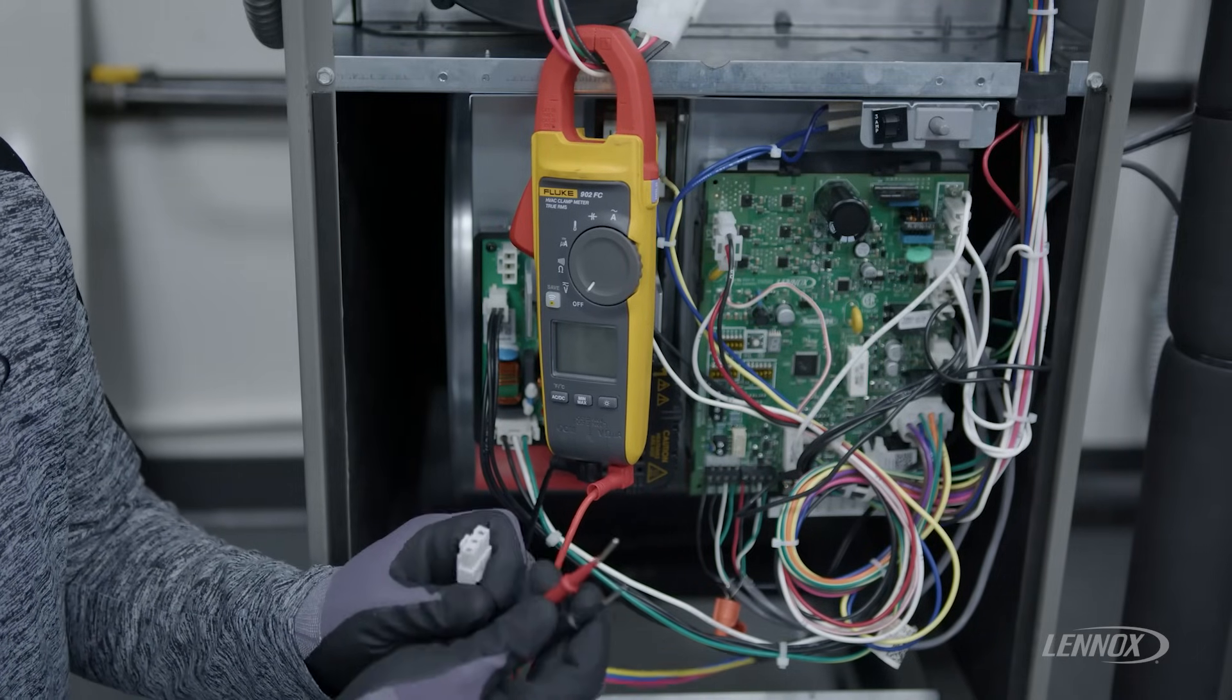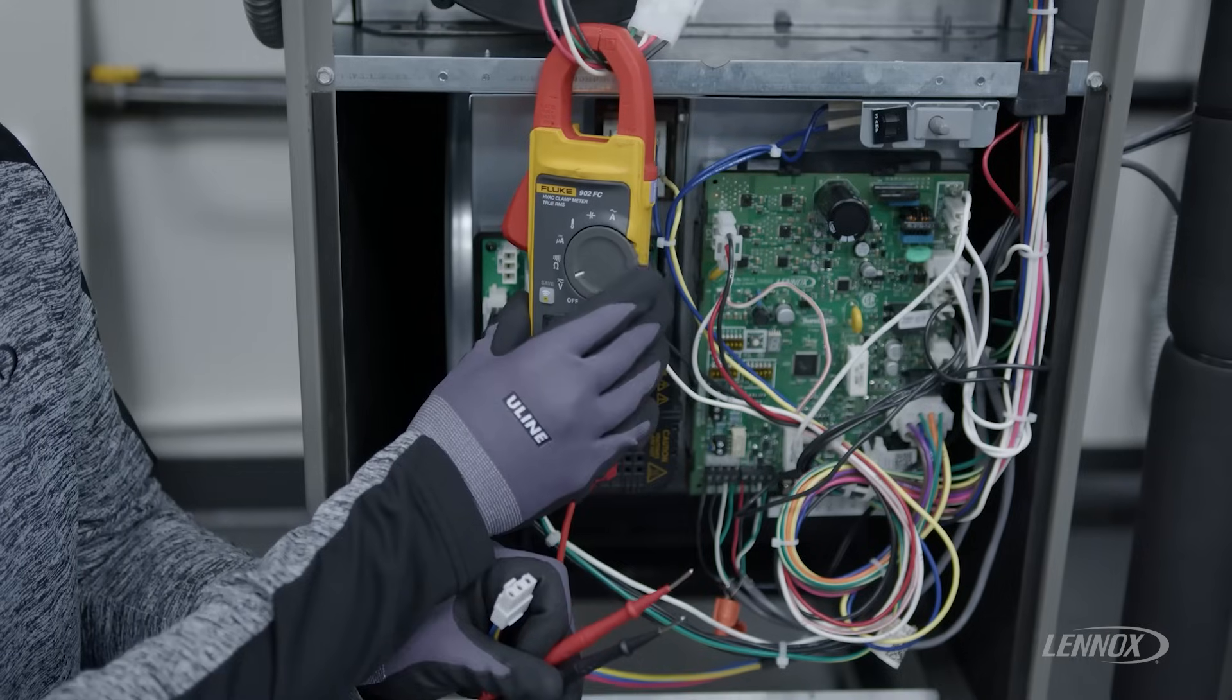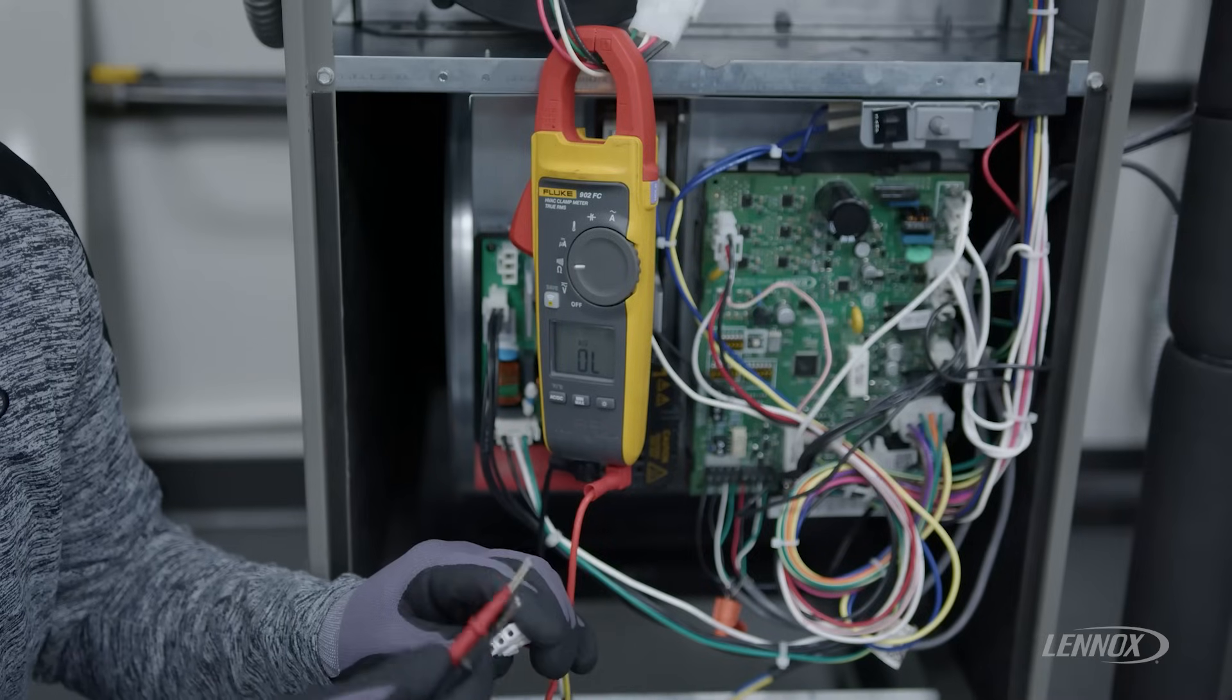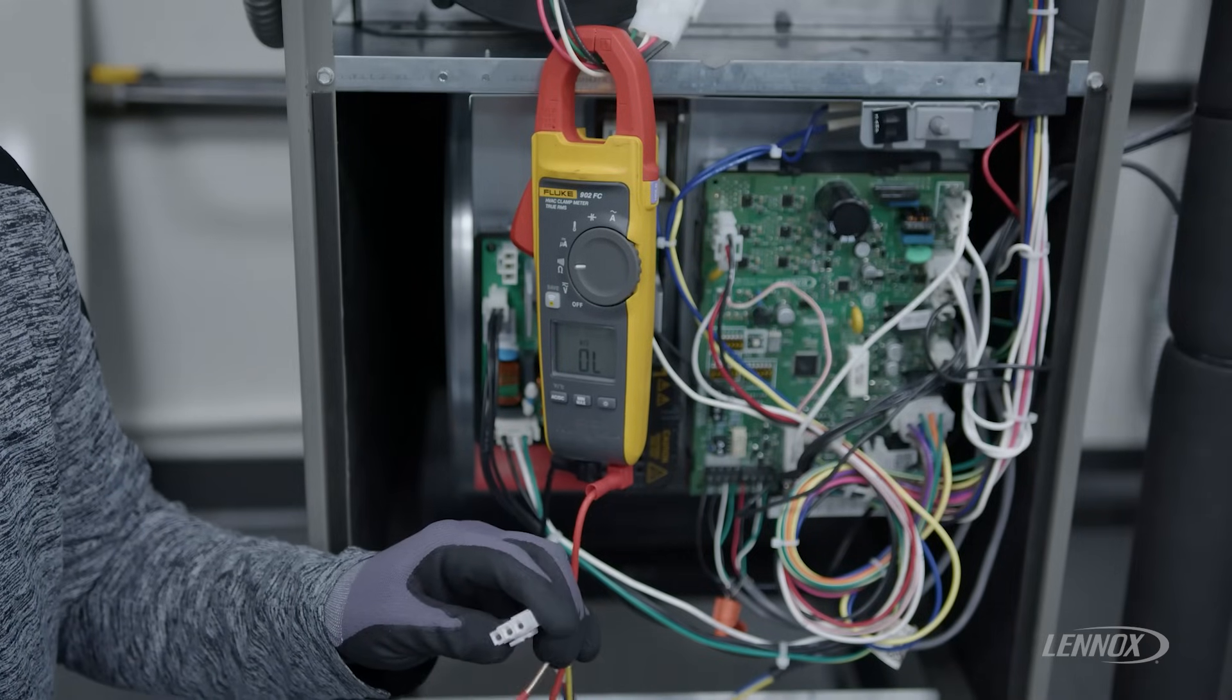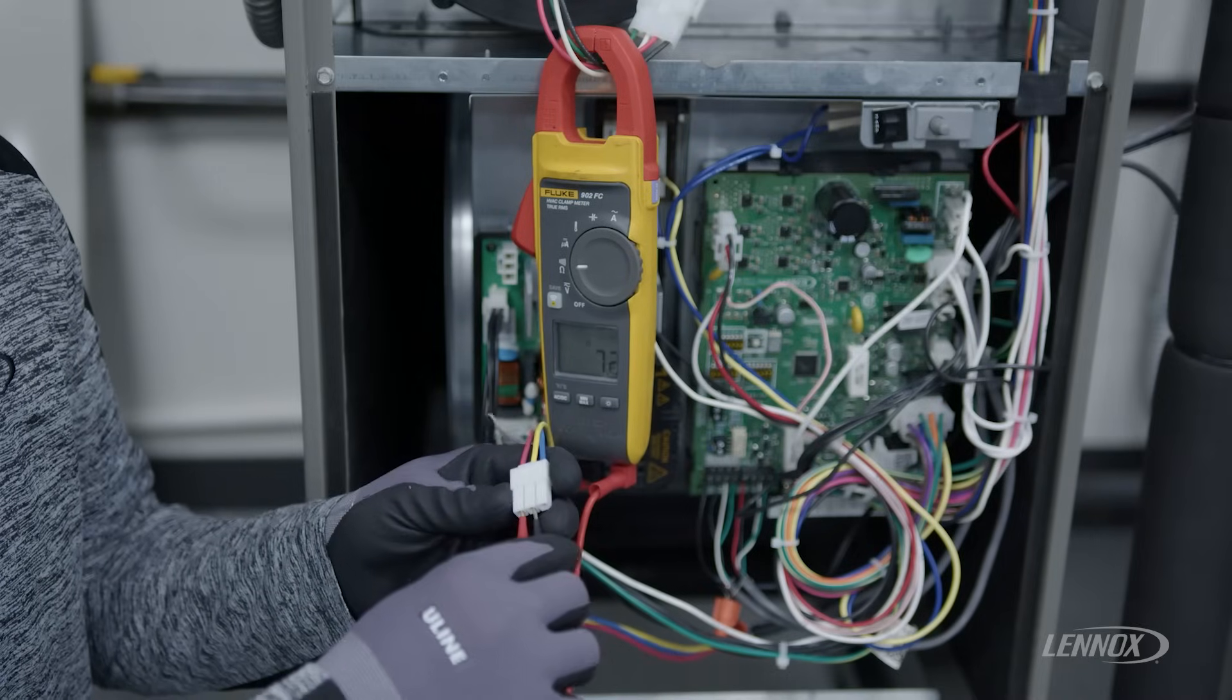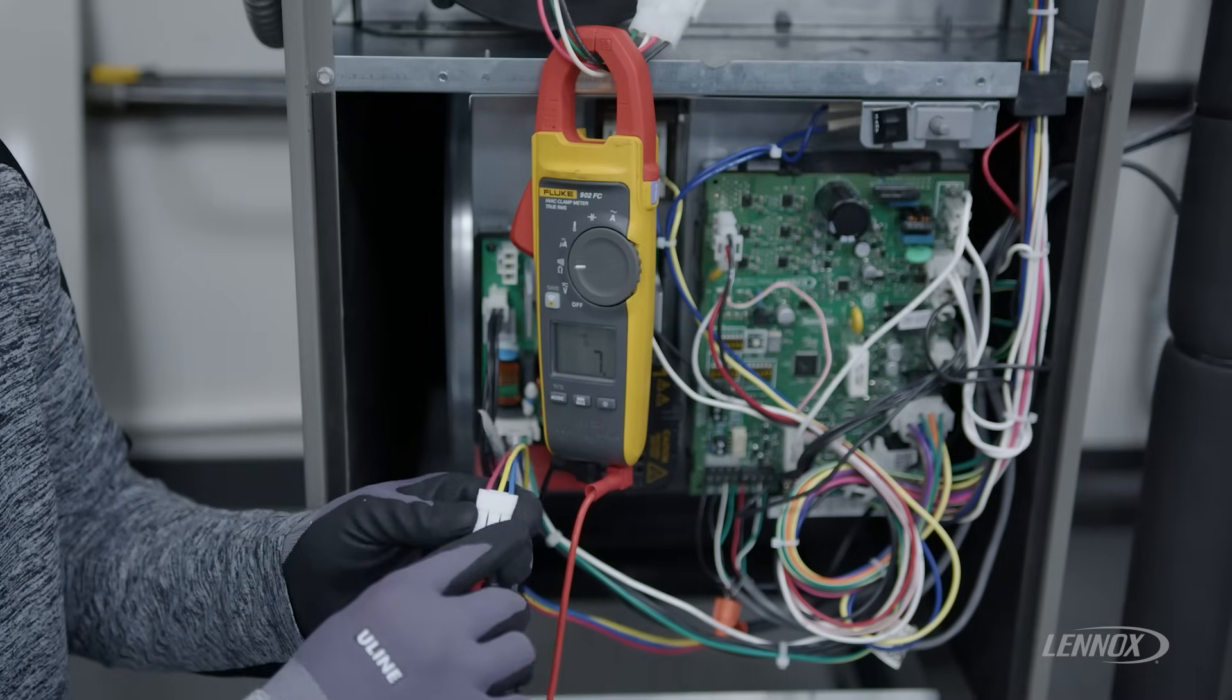To check the motor, we want to set our volt ohm meter to the ohm scale, and we want to verify our resistance reading between each winding of the motor. To do that, take each lead and go from each wire to each other wire and record your resistance.